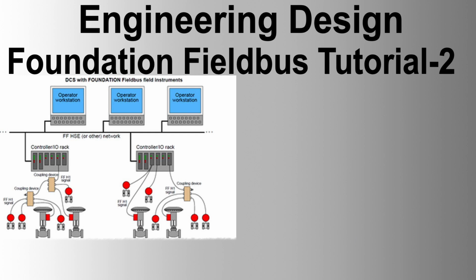The proportional integral derivative block is designed to provide standard PID control functionality. The PID block receives process variable inputs and outputs control variables to regulate the process according to the PID algorithm. PID algorithm: proportional P, integral I, and derivative D components. These components work together to regulate the process by adjusting the control output based on the error, the accumulated error, and the rate of change of the error. Control parameters gain, reset, and rate define the behavior of the PID control.